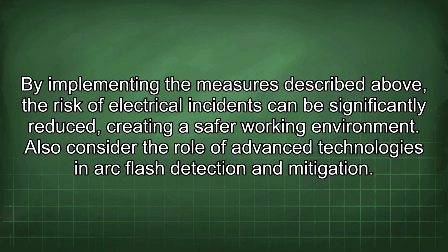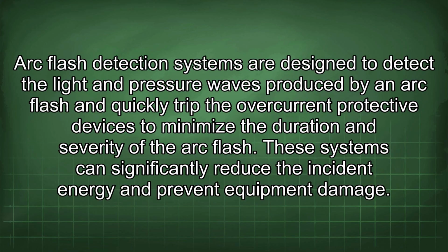Also consider the role of advanced technologies in arc flash detection and mitigation. Arc flash detection systems are designed to detect the light and pressure waves produced by an arc flash and quickly trip the overcurrent protective devices to minimize the duration and severity of the arc flash. These systems can significantly reduce the incident energy and prevent equipment damage.